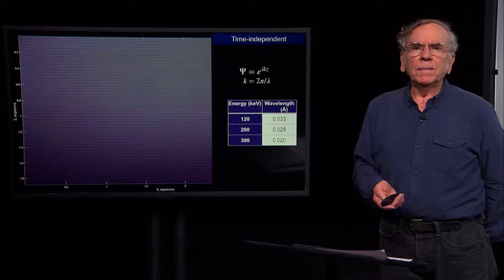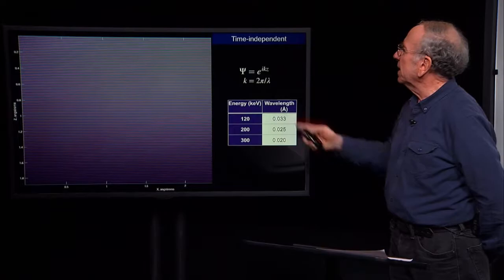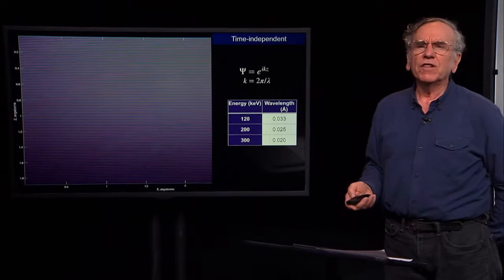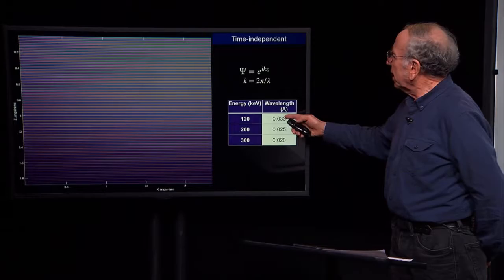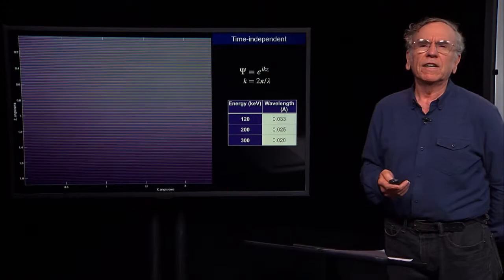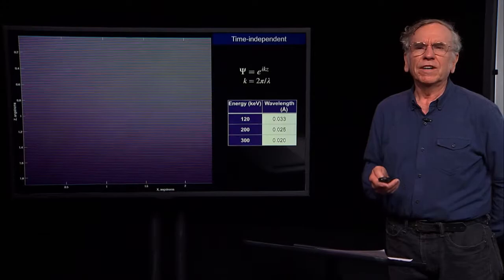For our purposes, we don't need to watch the propagation of the electron. The electron wave function I'm going to use today is time independent — it's e to the ikz. k is a constant called the propagation constant, like one over the wavelength. It shows how fast the phase changes as you move in the z direction. The electron wavelengths are really quite small. The three most popular voltages for cryo-EM microscopes are 120, 200, and 300 kV. We'll be talking about 300 kV electrons today, which have about a 1/50th of an angstrom wavelength.